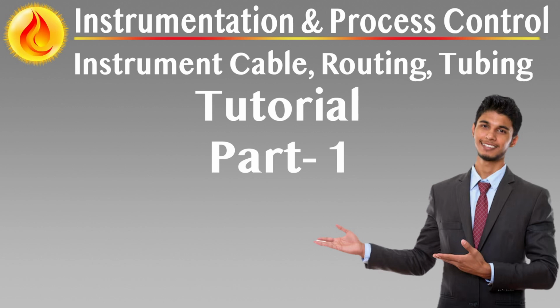For long distance runs, exposure to EMI, or lightning-prone environments, fiber optic cabling is preferred due to its immunity to electrical interference, non-conductive nature, and high data throughput. Digital instrumentation, including remote I/O systems, analyzers, and data acquisition networks, must be matched with appropriate cable types that support required bit rates, propagation delay limits, and voltage levels. CCTV and video feeds, particularly analog systems, should use coaxial cables with 75 ohm impedance, while digital video over IP may transition to Cat6, Cat7, or fiber optic lines.